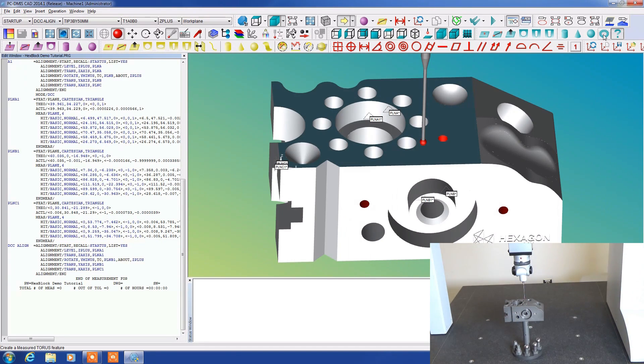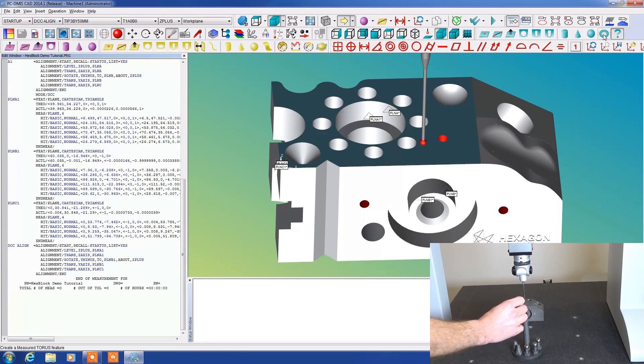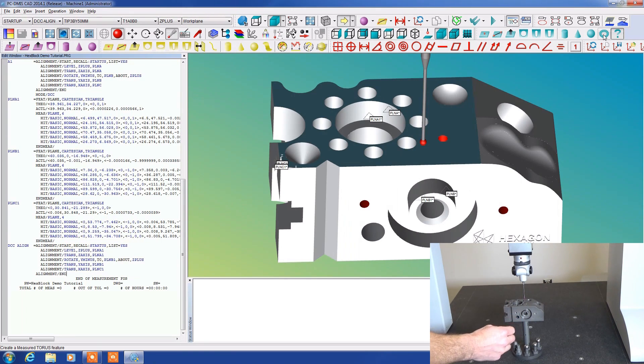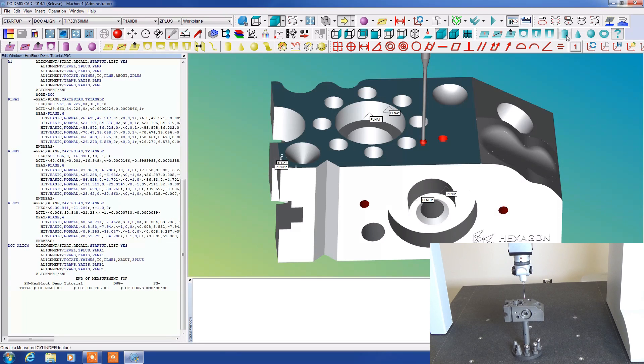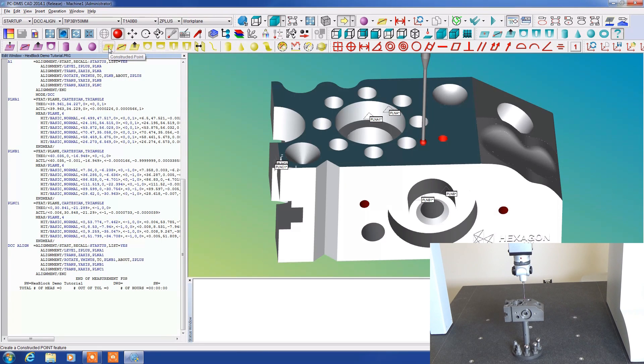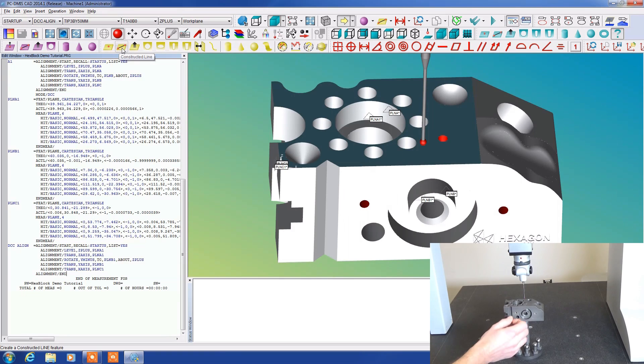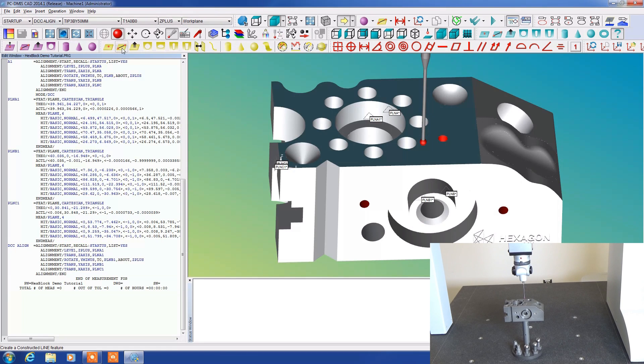Instead what you can do is measure these two planes, take several hits up and down these two planes, and then in order to find this intersection we're going to use a different set of controls. These yellow icons are called constructed points. Say for instance we measure this plane and this plane, we have those two planes in memory. They're right here on our CAD model.